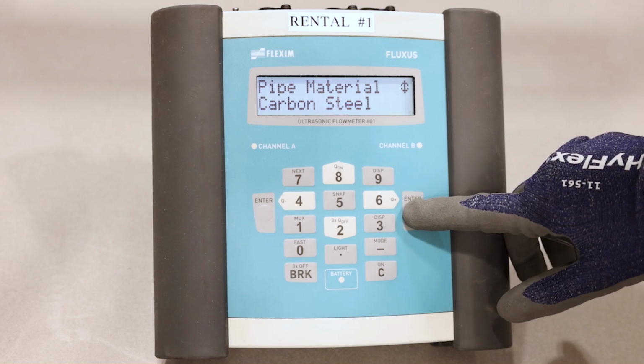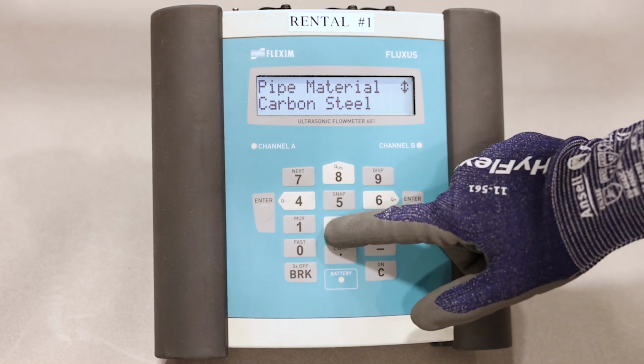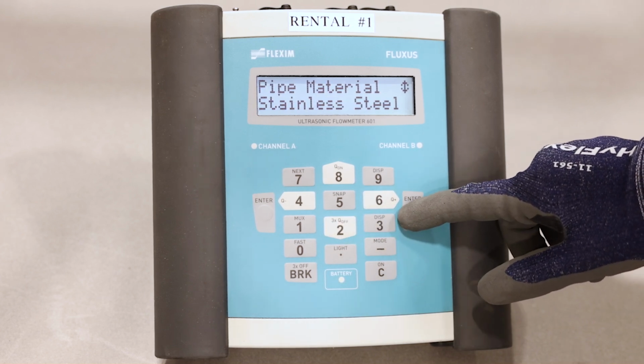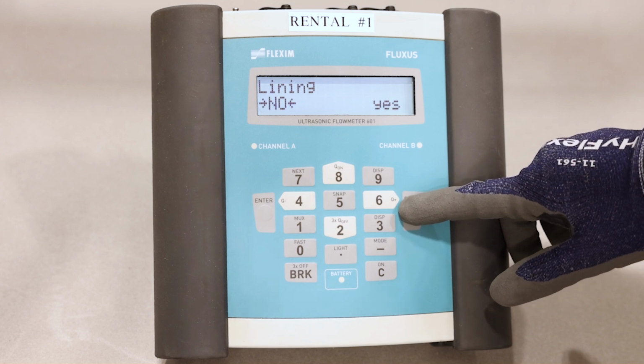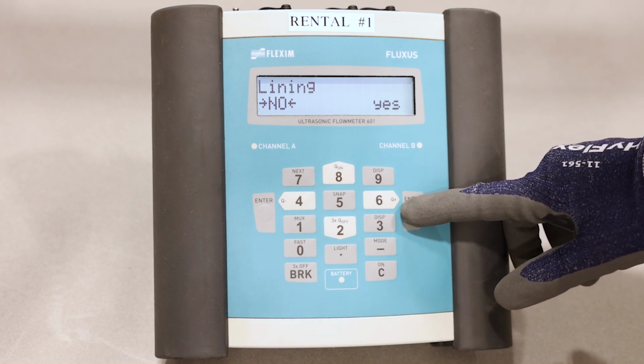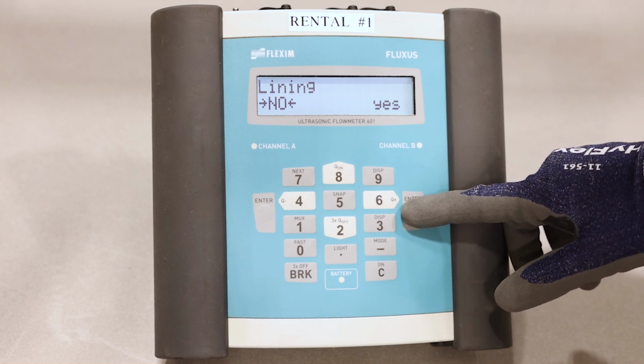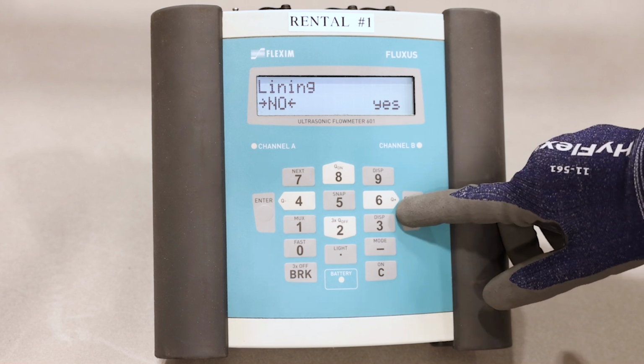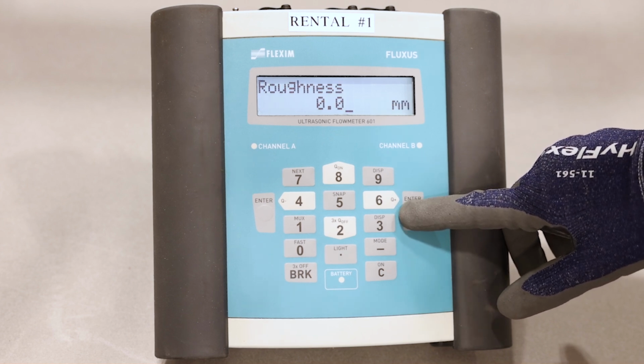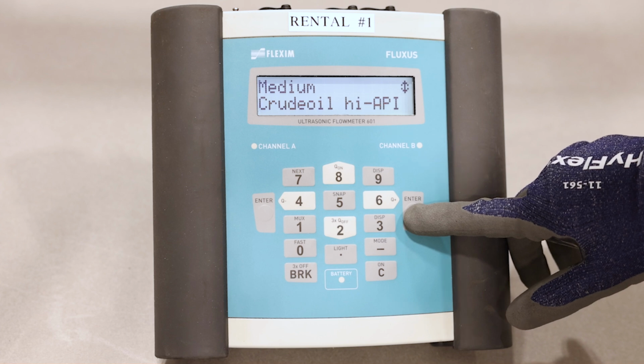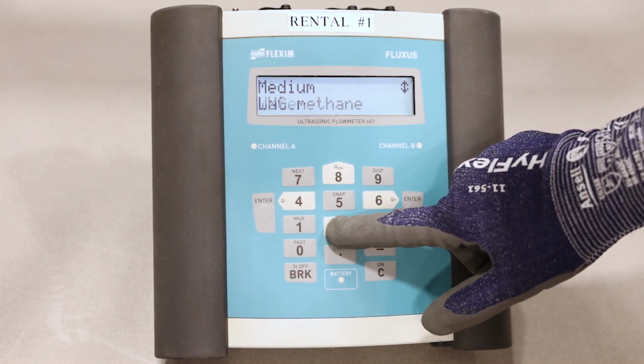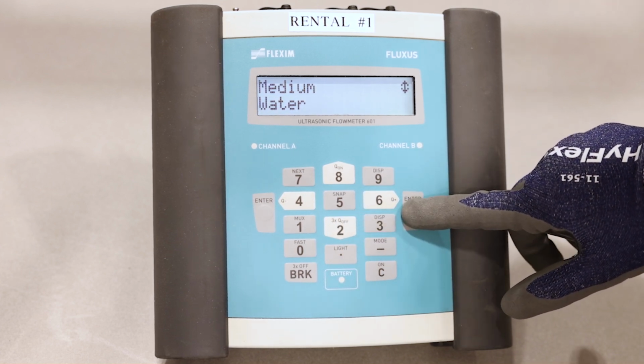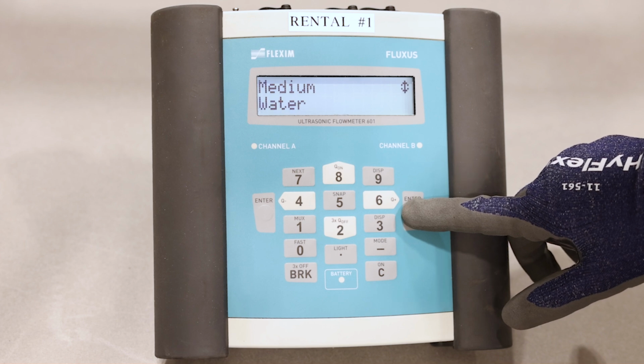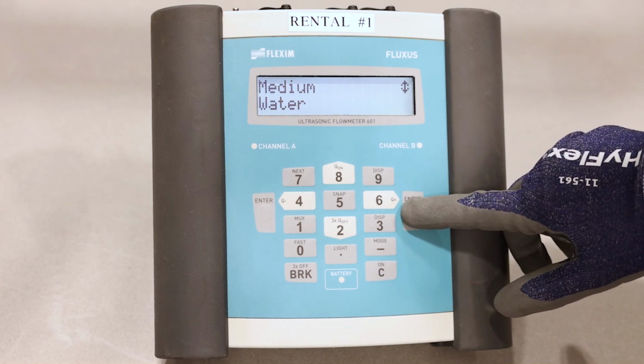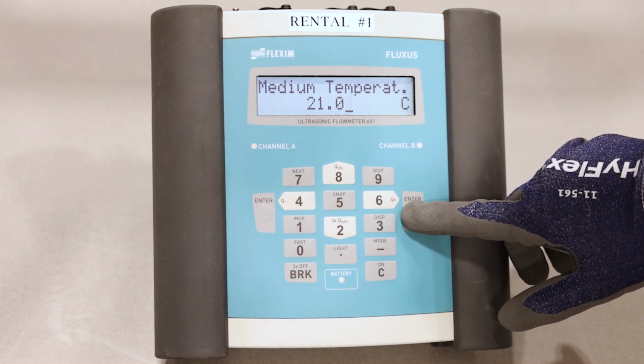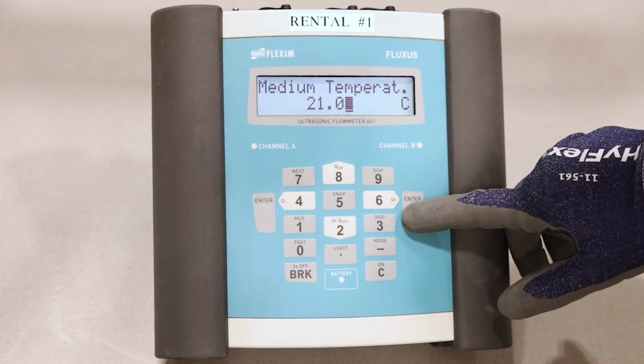Scroll over to your pipe material, in this case carbon steel. If your material is not shown, pick other material and it'll ask you for that material's speed of sound. We don't have any lining, no roughness, our medium is water, and the same goes if your medium is not shown, pick Other and enter the medium speed of sound for your process. Lastly, the temperature is 21 degrees Celsius.